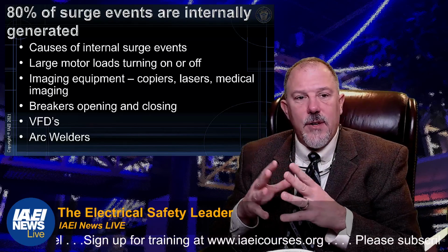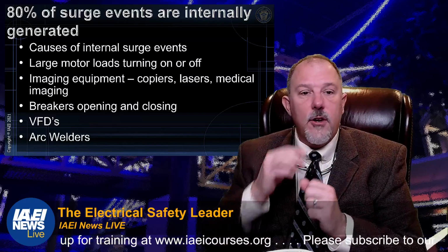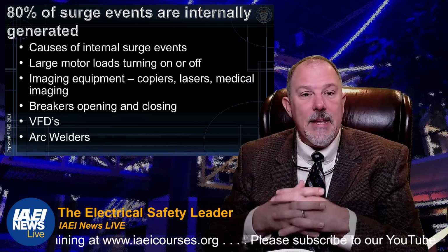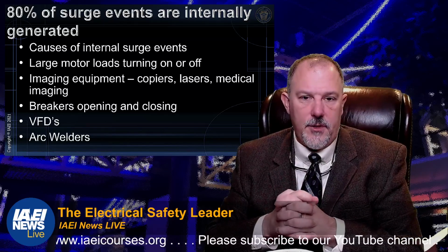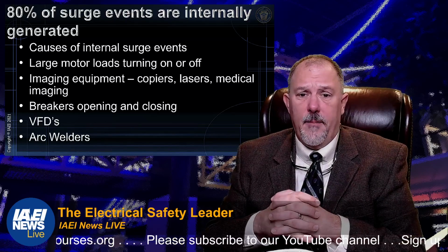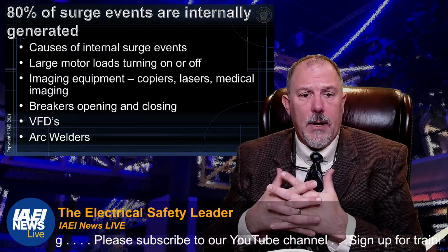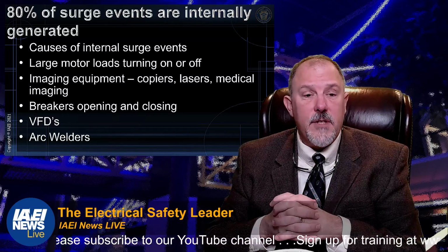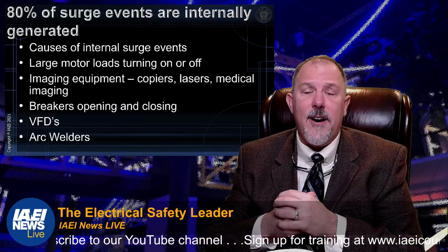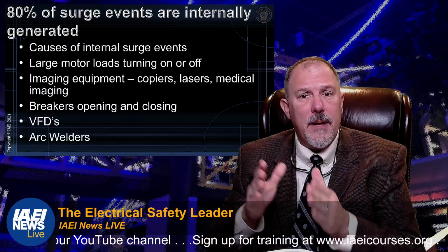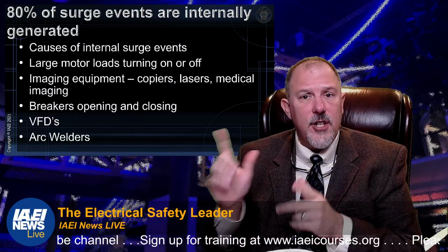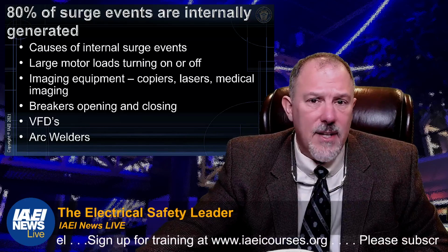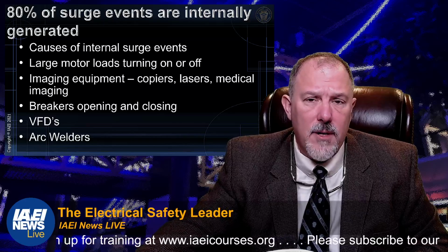80% of surge events are internally generated. Causes of internal surge events include large motors turning on or off, imaging equipment, copiers, lasers, medical imaging, breakers opening and closing, variable frequency drives, arc welders. There are a lot of different reasons, but 80% come internally and not just from external events like lightning or capacitor switching.